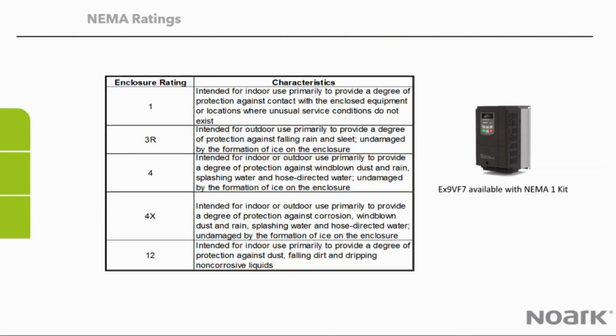So, more highlighting the enclosure and environmental ratings. As I noted before, we have the ability to have the drive alone with a NEMA 1 kit, so you could install it on a wall in an electrical room without any need for an enclosure. But if you're dealing with other environments, outdoor, water, corrosion, or extreme amounts of dust, then you'll need to consider enclosures of the appropriate type for those environments to put the drive in.